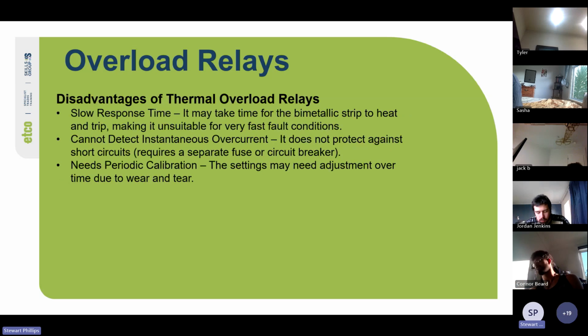Cool, so disadvantages of them. They've got a slow response time and may take time for the bimetallic strip to heat and trip, making it unsuitable for very fast fault conditions, but that's why we have our HRC fuses and our MCBs. It cannot detect instantaneous overcurrent and does not protect against short circuits. It requires a separate fuse or circuit breaker, and it needs periodic calibration. So the setting may need adjustment over time due to wear and tear.